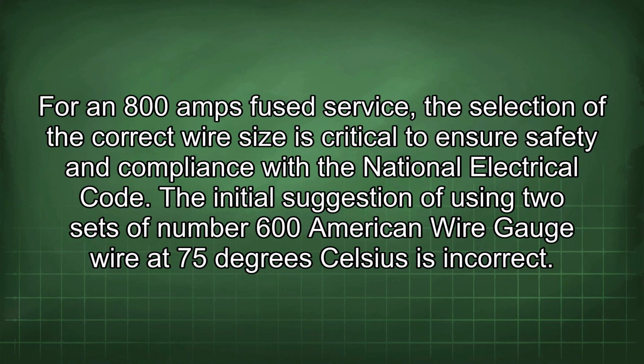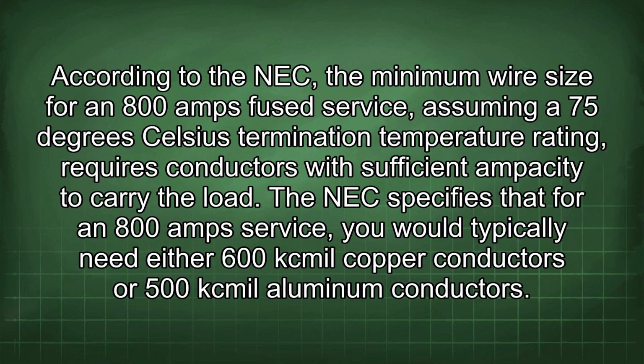For an 800 amps fused service, the selection of the correct wire size is critical to ensure safety and compliance with the National Electrical Code. The initial suggestion of using two sets of number 600 American wire gauge wire at 75 degrees Celsius is incorrect. According to the NEC, the minimum wire size for an 800 amps fused service, assuming a 75 degrees Celsius termination temperature rating, requires conductors with sufficient ampacity to carry the load.